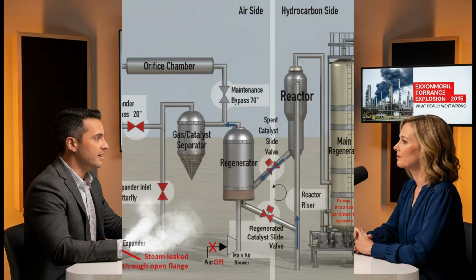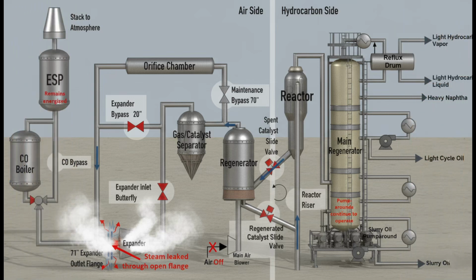Okay, which brings us to the final fatal management decision on the morning of Wednesday, February 18th. The maintenance crews needed to get inside that vibrating expander to inspect the damage. Right, and to do that safely, they needed to install a blind flange to completely isolate it from the rest of the system. And as soon as they cracked open the expander outlet flange to get ready, steam started pouring out of the opening.